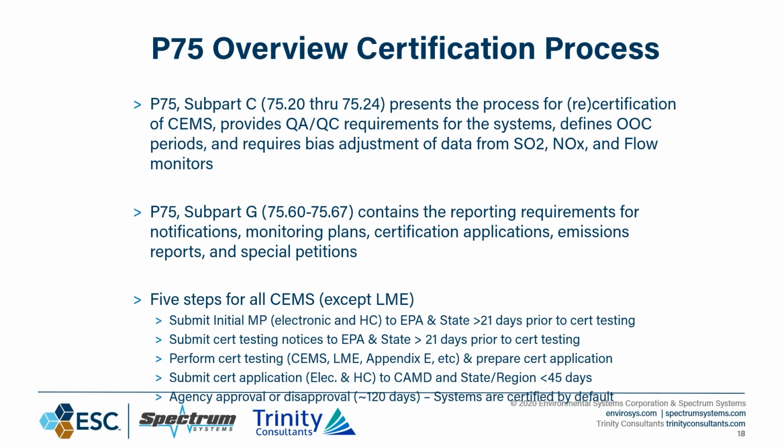But there are 5 steps that every CEMS has to go through, with the exception of LME, which has a slightly shorter list. You want to submit your initial monitoring plan. That would include the electronic and hard copy, generally to EPA and the state, 21 days prior to your test. Same time you would submit those certification test notices, 21 days.